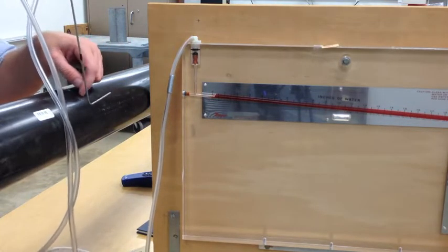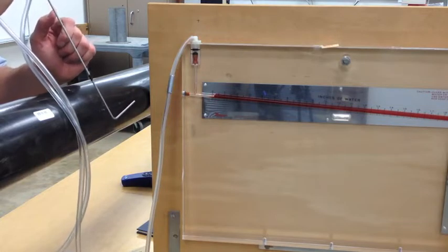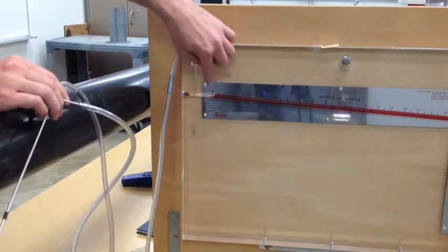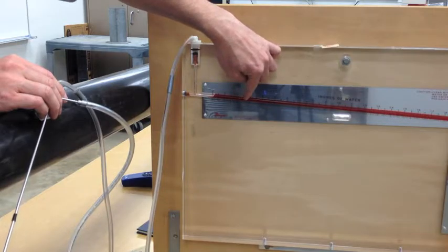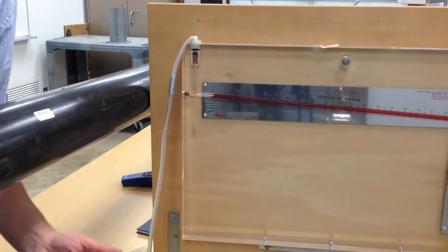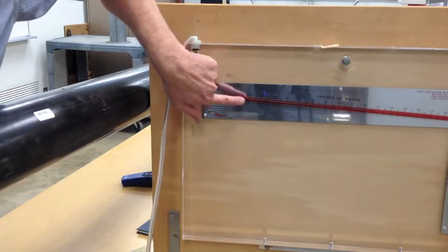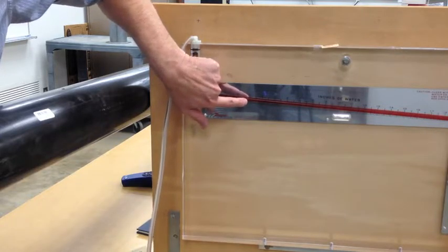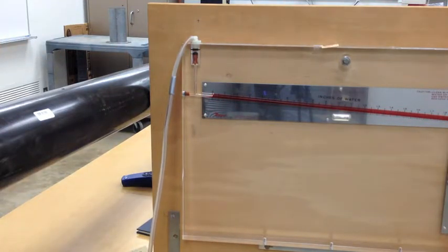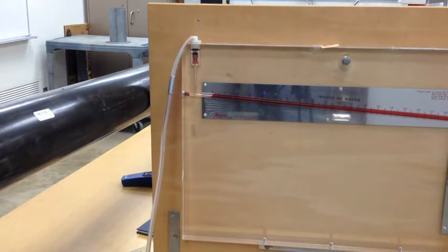Short of doing a traverse where you take measurements at all the different locations throughout it, that would be your best, most accurate. But the water column got sucked this way just a little bit past 0.3. I'm going to call it 0.312 because I used an electronic meter earlier and that's what it gave me. But you can basically see that it was about 0.31, and it was hard to get beyond that with this measurement. But about 0.31 was the positive velocity pressure for there.